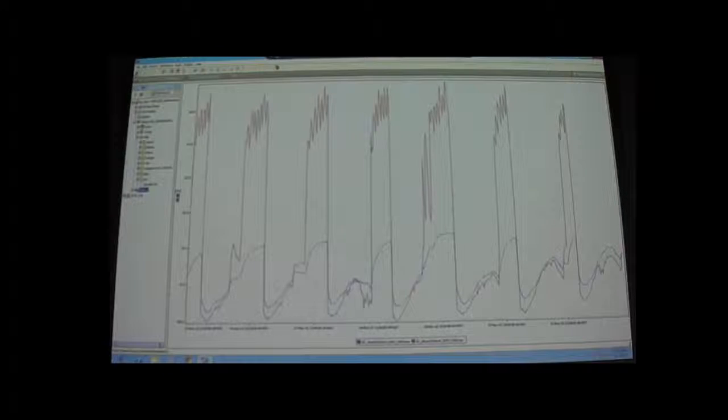Yeah. And then if you want to purge it, you basically go into your history and you go into database maintenance, and this is where you can delete anything back behind a certain date, or if you want to get rid of a point entirely, you can do it here. But the supervisor is designed essentially to pull all that data, and we can pretty much keep it for infinite days, because it just doesn't take up that much of our space, even if you're already doing it.